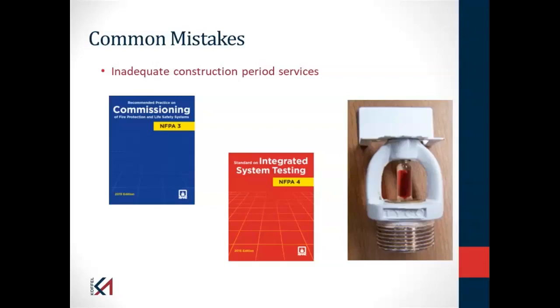If I get out of systems and talk about through penetration fire stop systems, I've been involved in numerous litigation cases where allegations were made that it was not done properly. That could have been picked up during construction much easier than post-occupancy. On the far right of the slide is a counterfeit sprinkler. To many of us, it looks like a legitimate sprinkler. It's even got a Tyco marking on it. So Tyco's a manufacturer.